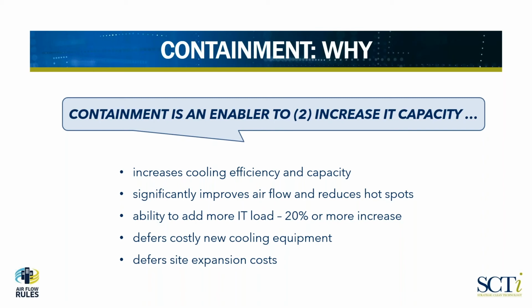And the other element that we've seen here, which we didn't make a note of, is that some sites say, well, I need a new cooling system because I don't have N+1 capacity or cooling capacity in the site. Again, by doing containment, we can prove to you that you now have N+1 cooling capacity, because your cooling systems don't have to operate as hard as before. And with the increase in return air temperatures, they have now achieved greater cooling capacity than they had previously.